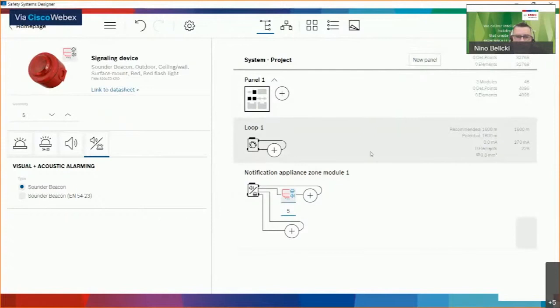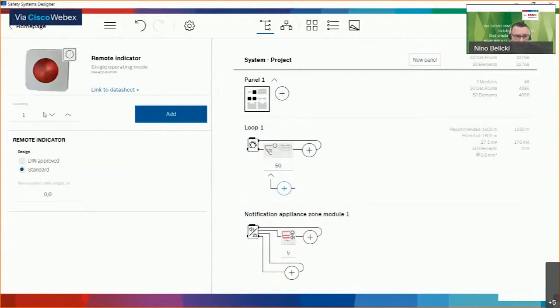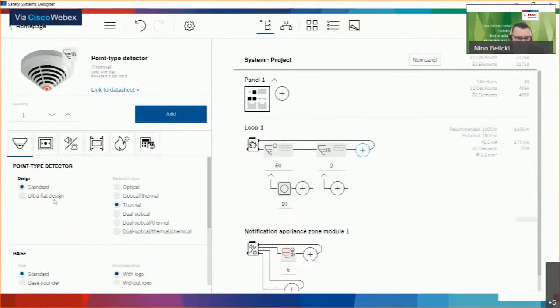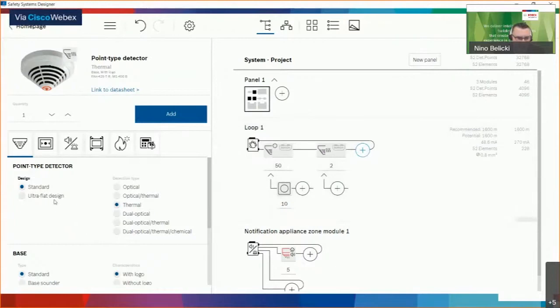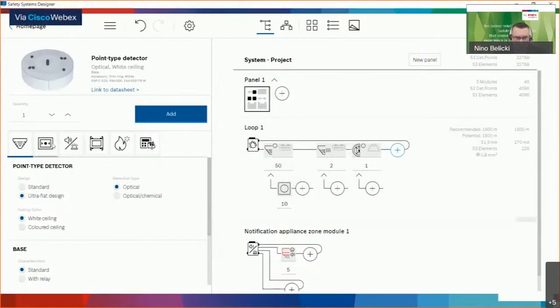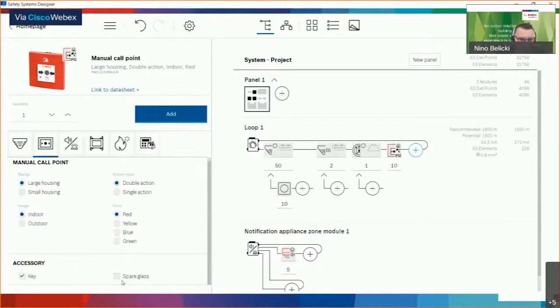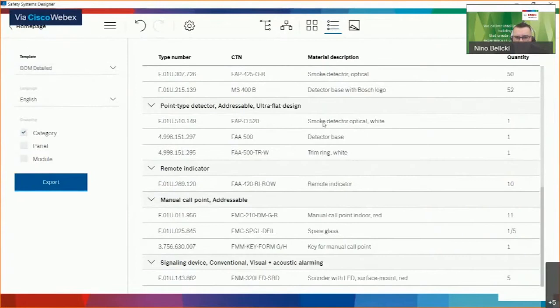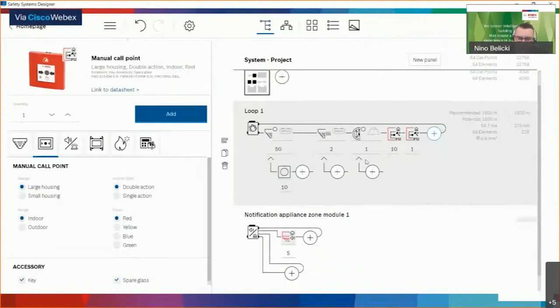I can start adding items to the loop — let's say 50 detectors. We can also add remote indicators, let's say 10. Then I can press plus and add a thermal detector. For the lobby, I can add the ultra-flat design Bosch detector. In the manual call points section, we can also add some manual call points. In the lower part you have all accessories related to this product, so we can also add spare items. In the bill of materials list, this is the BOM — it's automatically filled with everything added in the working dashboard, including all the modules in the Bosch panel. Rails and cables are all calculated automatically.